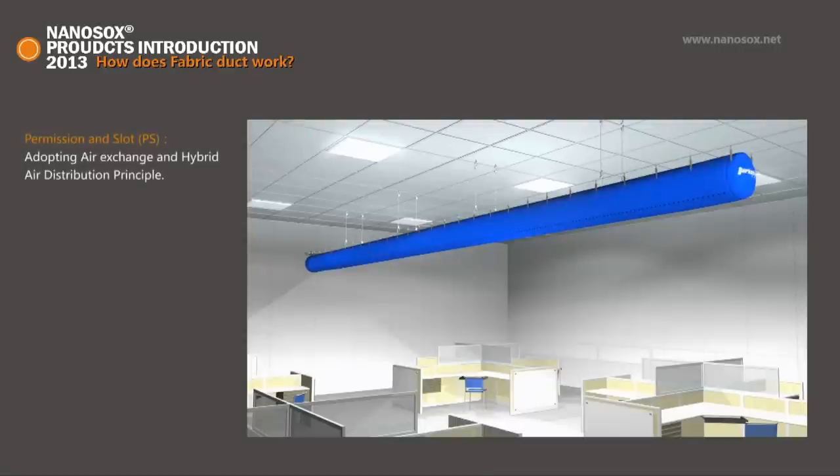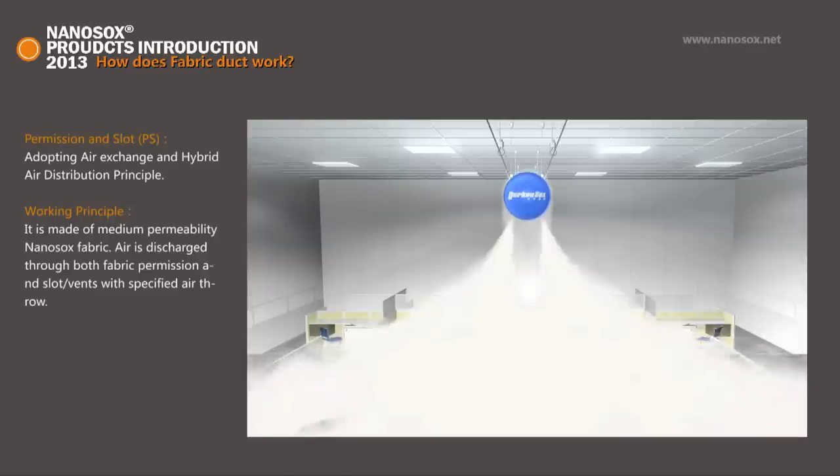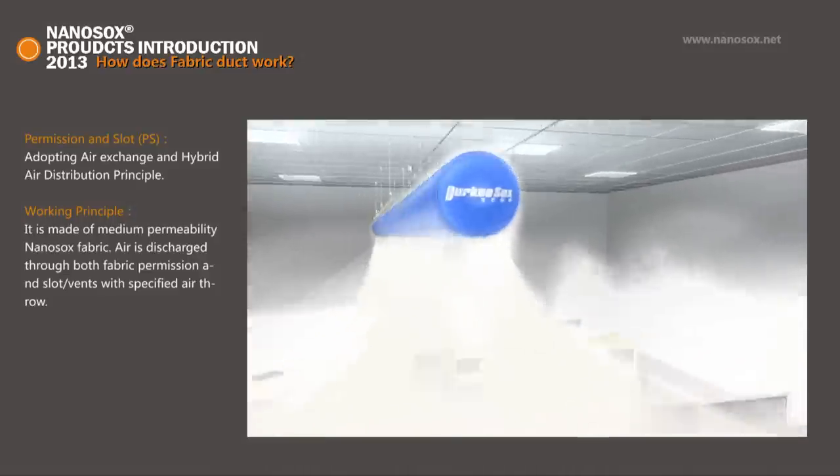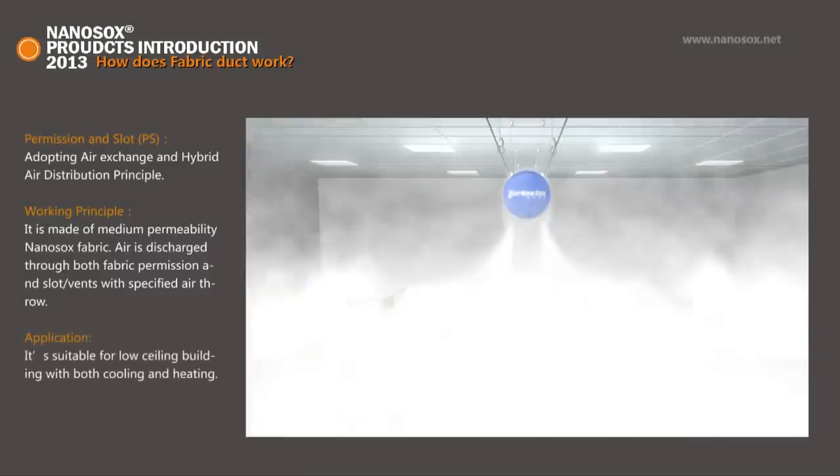Permeation Slot PS: It is made of medium permeability Nanosox fabric. Air is discharged through both fabric permeation and slots or vents with specified air throw. It is suitable for low ceiling buildings with both cooling and heating.